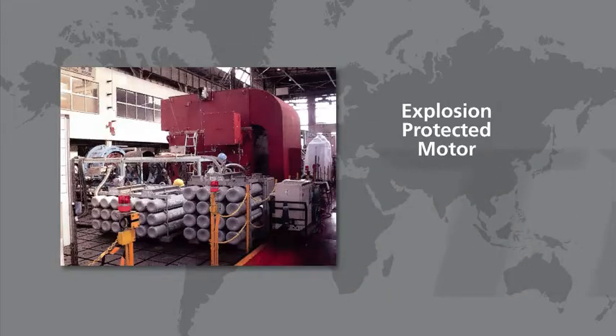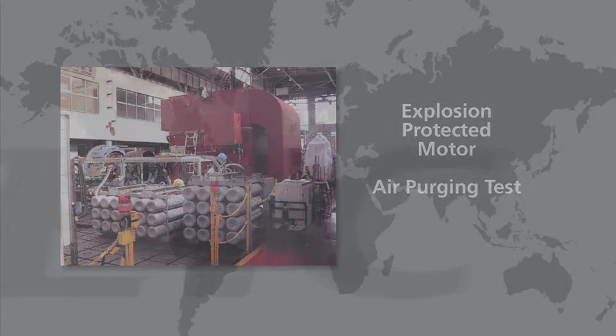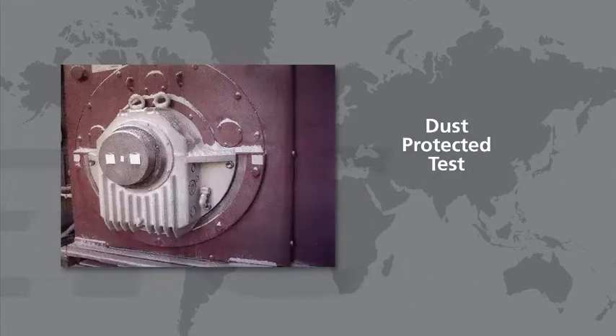TMEIC has developed explosion-protected motors for use in oil, gas, and petrochemical plants where combustible gases may be present. For insurance purposes, this motor is pressurized and undergoing a factory air purging test to be certified by the British certification agency, BASEEFA. For harsh environments such as high temperatures, moisture in spray, and dusty conditions, we design and test special motors to qualify for a specific IP protection rating.